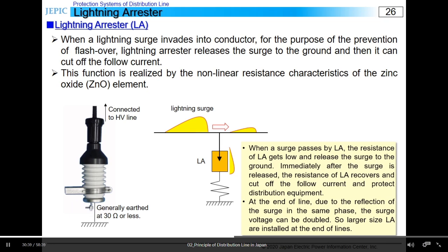When a lightning surge is passing by where a lightning arrestor is, the insulation resistance of a lightning arrestor between line and the ground becomes low enough to release the surge to the ground, and then, once the surge voltage reduces below a certain value, its insulation resistance immediately recovers to cut off the follow current. In the case of a strong lightning, a large surge exceeding the capacity of a lightning arrestor might flow, resulting in a burnout of lightning arrestor, but installing together with ground wire can reduce the surge.